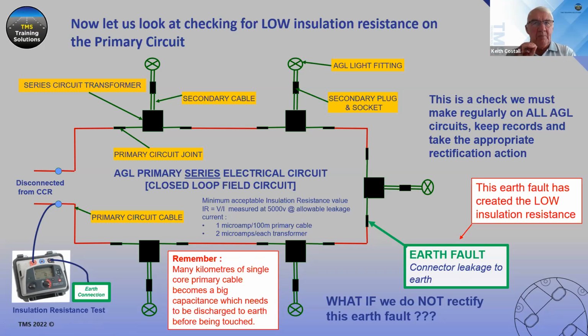And the reason why we're testing it for compliance at 5,000 volts with an appropriate insulation resistance tester, commonly called the megger test, is because of the equipment: the isolating transformer, the connectors, the cable, whatever kind of cable we've got. It's usually a 6mm square single core current carrying conductor, insulated possibly with PVC, etc., but commonly with XLPE, cross-linked polyethylene insulation. We want to ensure that the security and the integrity of that circuit as a closed loop remains. When it doesn't, it's usually water or fluid leakage into a joint or a failure of the isolating transformer.